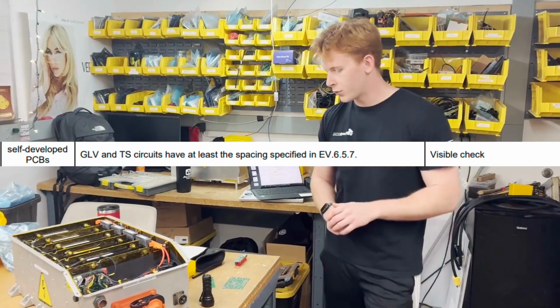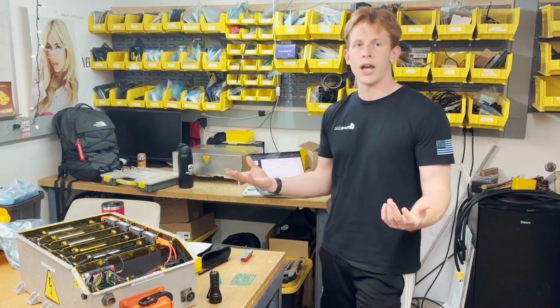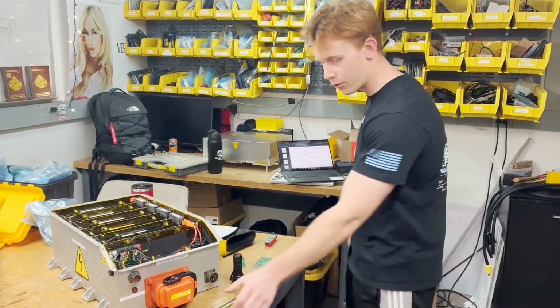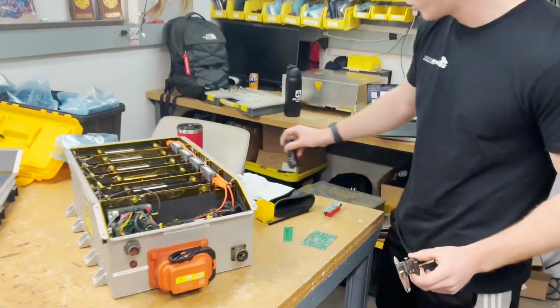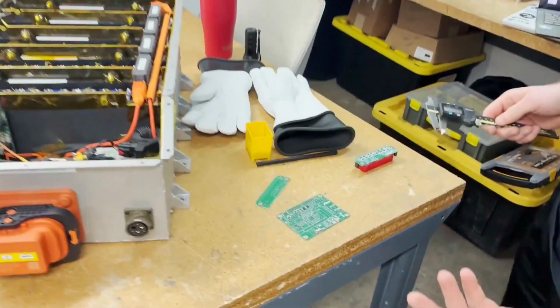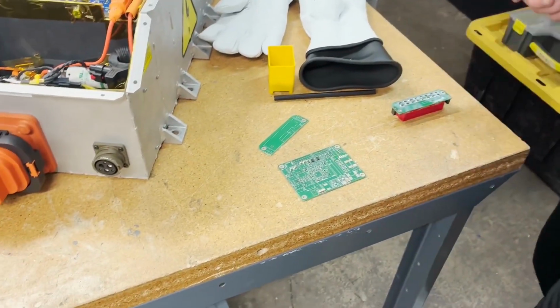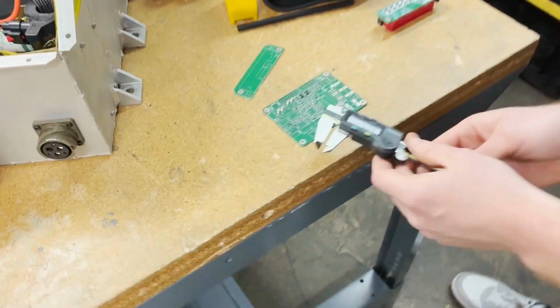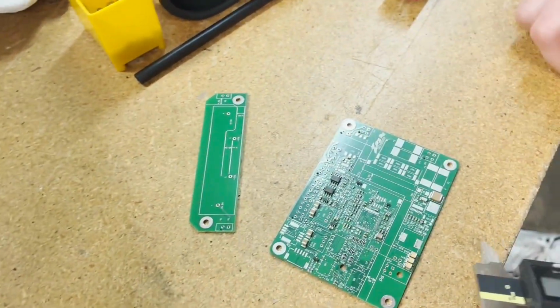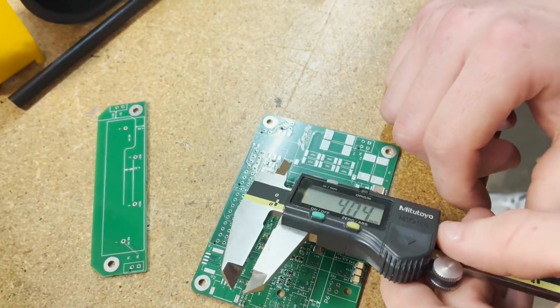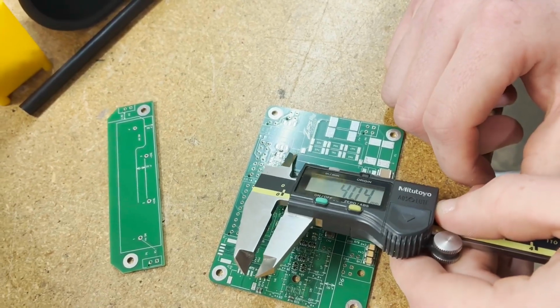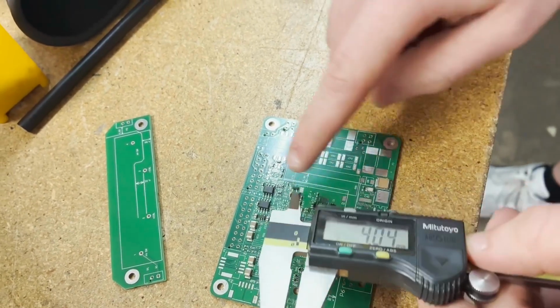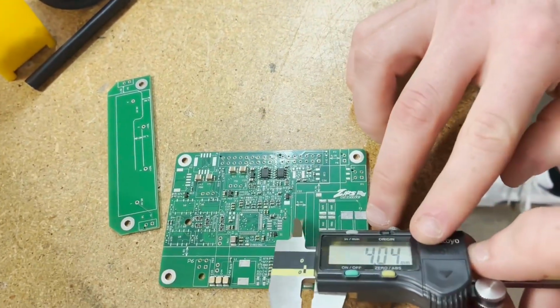As for low voltage and high voltage isolation on our self-developed circuit boards, you can see two of our boards here. These are the only two that have low voltage and high voltage circuits on the same PCB. You can see the distance between the gaps is labeled in the silk screen, exceeding 4 millimeters at the narrowest point, and again at the further point.